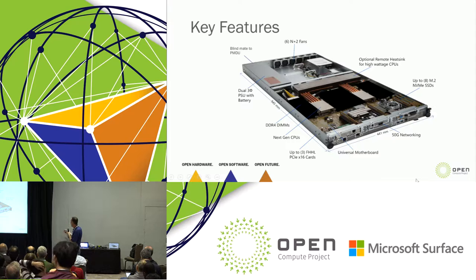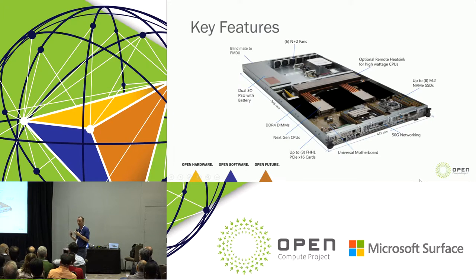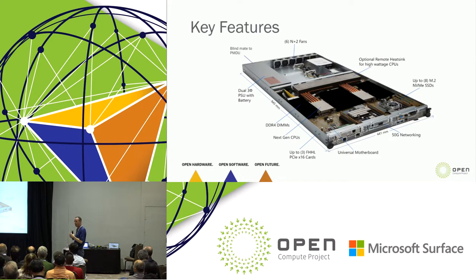You see lots of front I/O. In the rear you see blind mating PMDU. We don't want to be back there handling cables. We don't want to be back there changing out fans. We have adiabatic data centers, and when I put something out there that puts people in the hot aisle, they immediately hold me to account. Stay out of the rear, service it in the front, enable technologies going forward — that's the main tenet of what this platform is about.